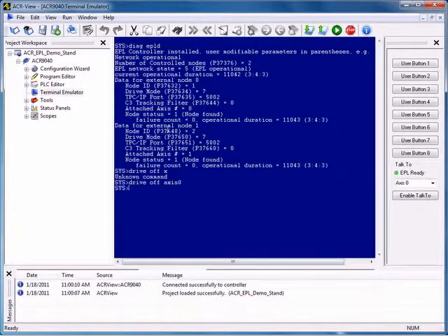I'm going to turn my drive back on. My drive just re-enabled. In order to be able to access the drives via their aliases, X and Y, I need to be at the program 0 prompt. To get to the program 0 prompt, I'm going to type PROG 0, P-R-O-G 0. Notice my prompt has changed to P00. I'm in the right place now.